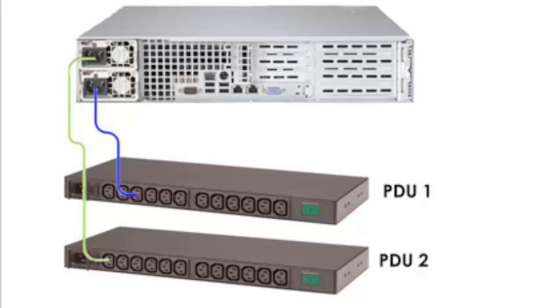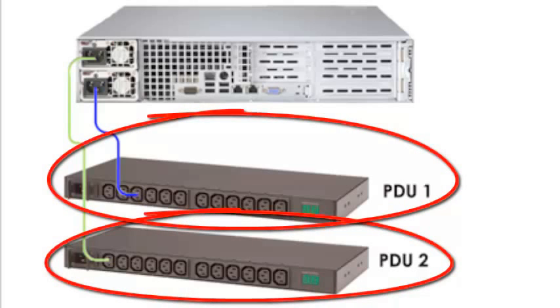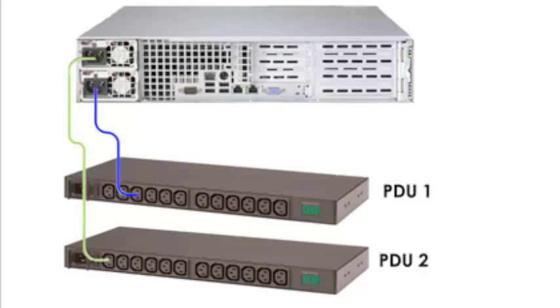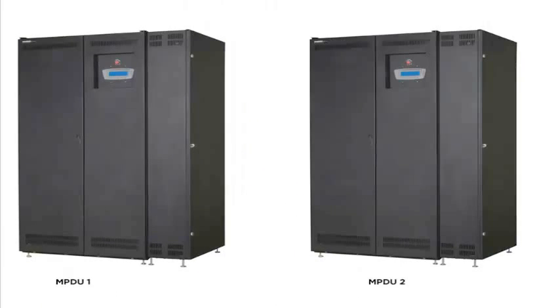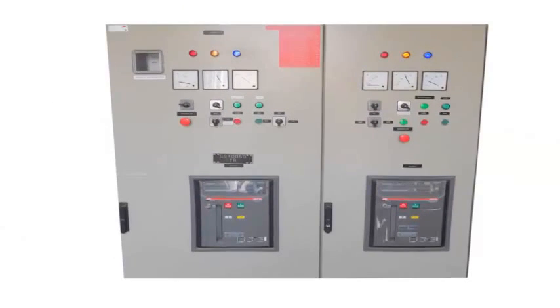Moving past the server level, we go to the individual PDU for the area, which is split into two different connections between two different PDUs. A PDU, or power distribution unit, is how power comes to the server. The PDUs actually connect another line back towards a master power distribution unit, or MPDU, which is a larger array giving redundancy to the PDU units, which are then controlled by an ATS, a transfer switch behind the MPDUs, which controls how power comes through.